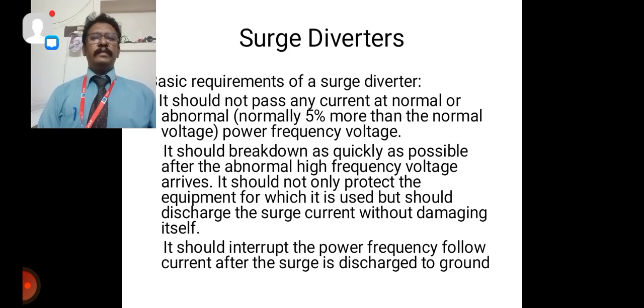Next, you can see here the basic requirements of a surge diverter. The first one: it should not bypass any current at normal or abnormal power frequency voltages. It should break down as quickly as possible after the abnormal high frequency voltage arrives. It should not only safeguard the equipment for which it is used, but should also discharge the surge current without damaging itself. It should interrupt the power frequency follow current after the surges are discharged to the ground.